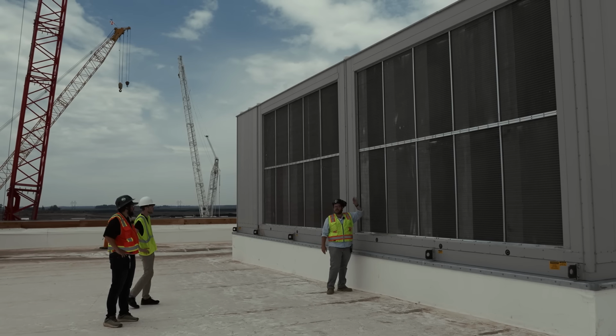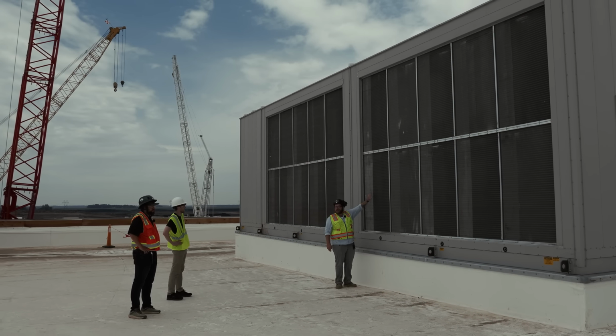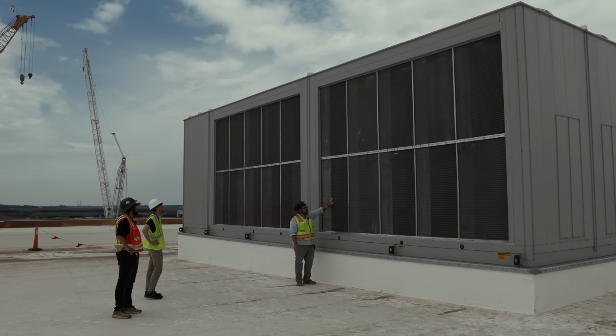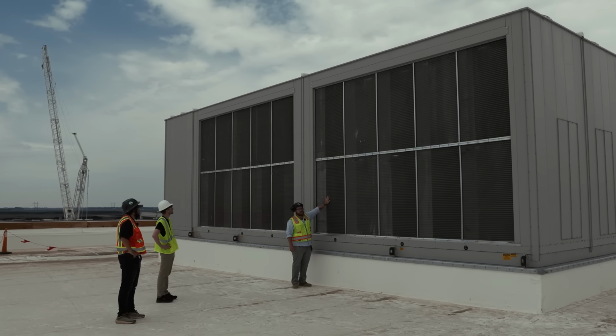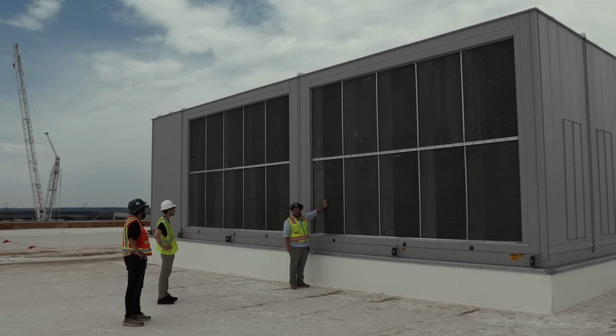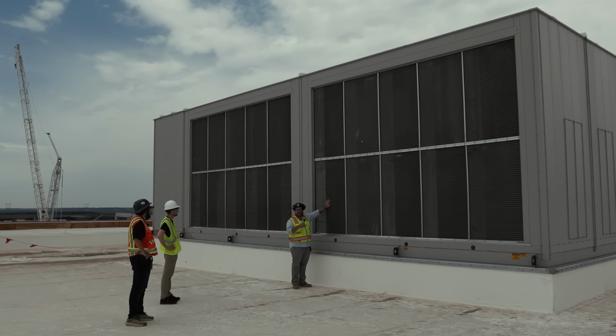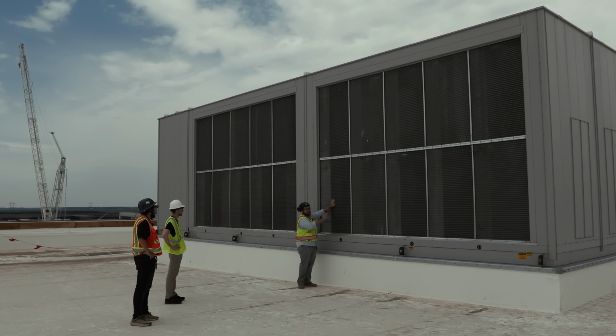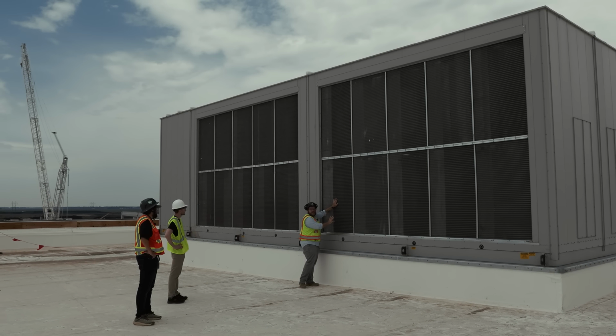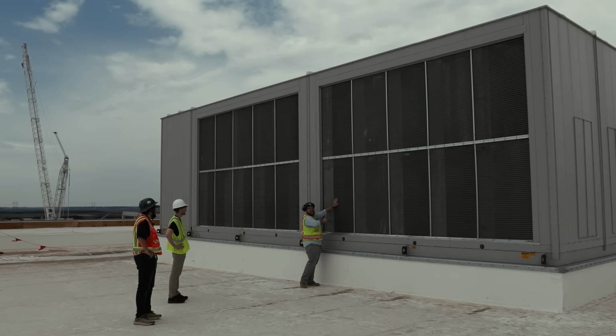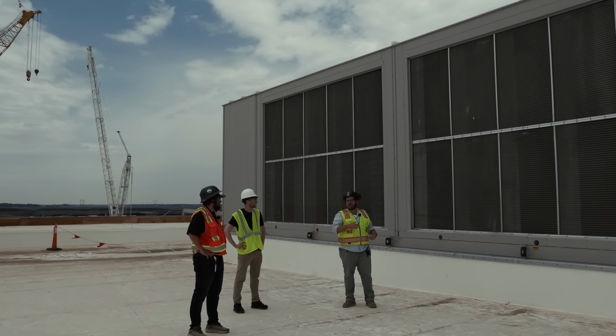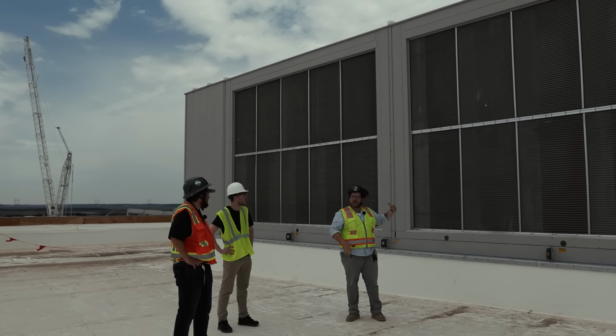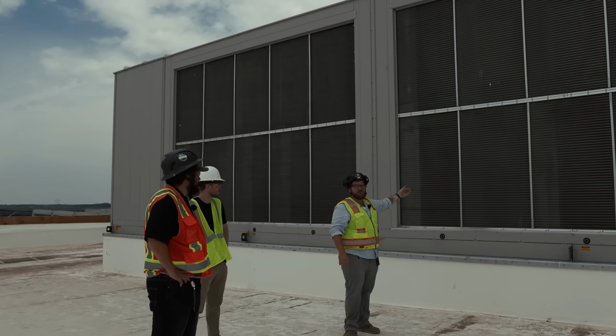So in that fancy, wonderfully drawn diagram that I made for you earlier, this is where the heat's rejected. After the compressor side of things, it's kicked out through these coil walls, and then the air is pulled up through the top, through the coil, taking all that heat out of that liquid and rejecting it out the top. Once we get above 58 degrees, the mechanical cooling kicks in, and we're using both walls.